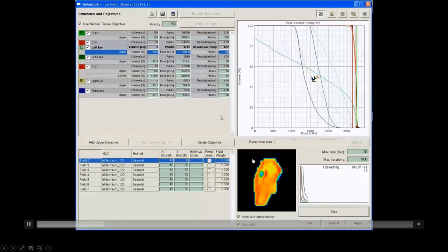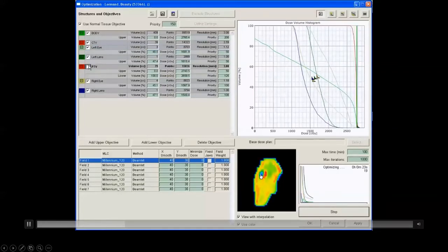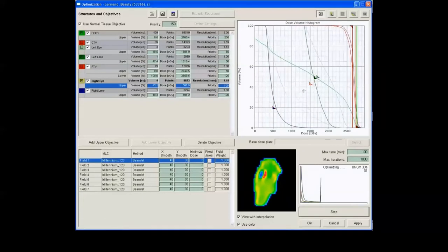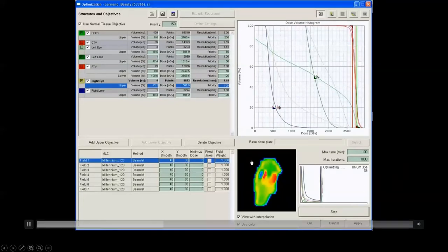So what we're seeing here, this is sort of a real-time fluence map, and you can kind of see this cold spot. Radiation dose plots are sort of like weather maps. The bluer you are, the colder you are, and then if you get down to having a black background, that means there's no dose being delivered in that area.